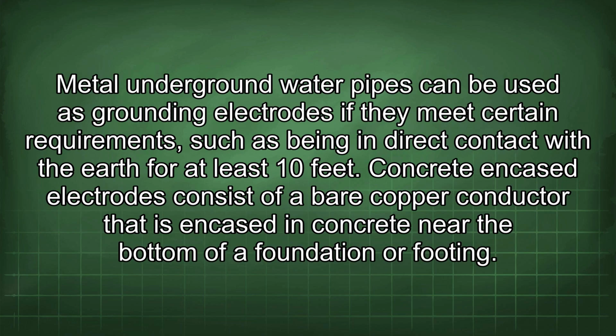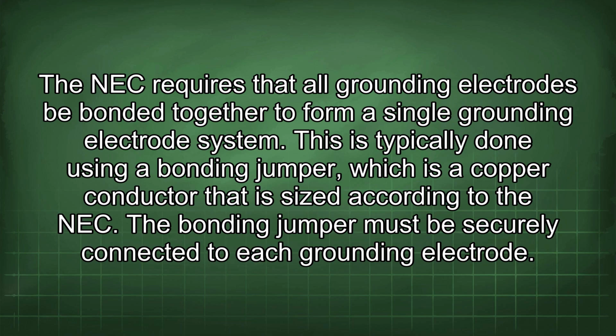Metal underground water pipes can be used as grounding electrodes if they meet certain requirements, such as being in direct contact with the earth for at least 10 feet. Concrete encased electrodes consist of a bare copper conductor that is encased in concrete near the bottom of a foundation or footing. The NEC requires that all grounding electrodes be bonded together to form a single grounding electrode system.